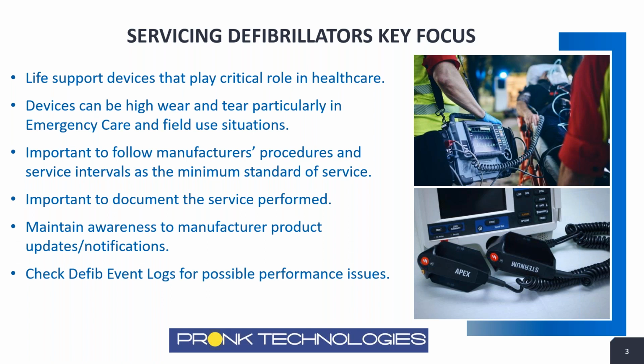Also, as part of our service and maintenance, or even when you receive a service call regarding some performance issues on the devices, it's really important to take advantage of the event logs that the defibrillator has. The devices have an event log where they capture any errors that occur. It's generally found in the service section of the defibrillator itself, and you can glean really good information from time to time on any errors that have been happening. If the nurse reports something, maybe you're not able to see it right away, check the event logs. Or if you're going to do a preventative maintenance, before you even get started, check the event logs, see if there's been any continuous errors that have been happening, any errors that could impact performance, something that could really help us make sure that we're servicing these devices the best we can.